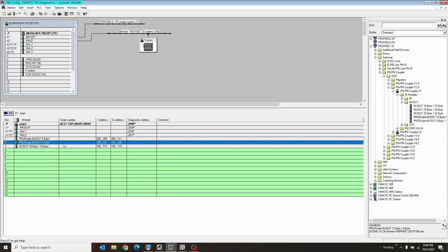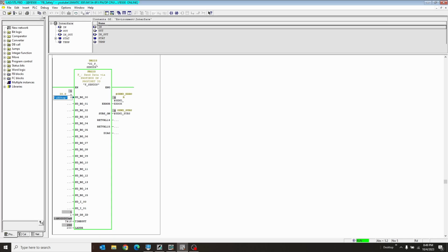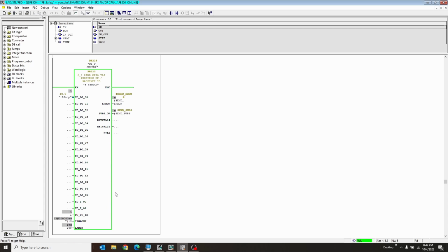There's a timeout and a logical address. The logical address 220 is referring to the 12 byte. So let's scroll down past the other regular safety logic to the end here. And I have the e-stop that I have on this PLC. And I'll push that and it goes off and click it back out and it comes back out to 1 again. Okay, cool. So that's working. So that's going into the SendDP. So this is the array of bits that'll go and show up on the receive side of the other guy. He also has a timeout and a logical address 200, which is this guy, for his assignment there.